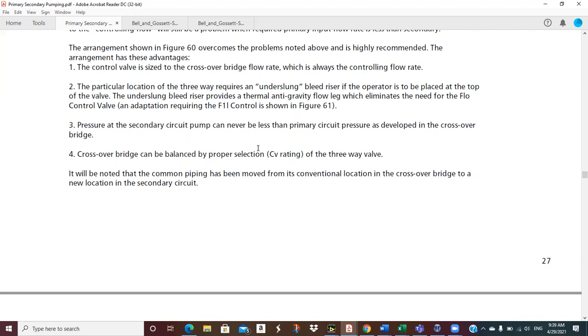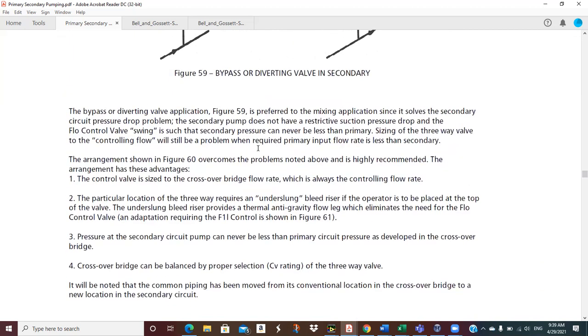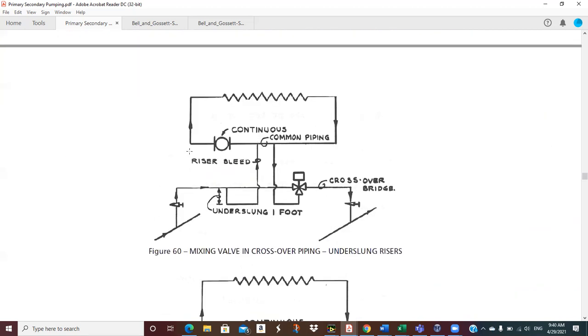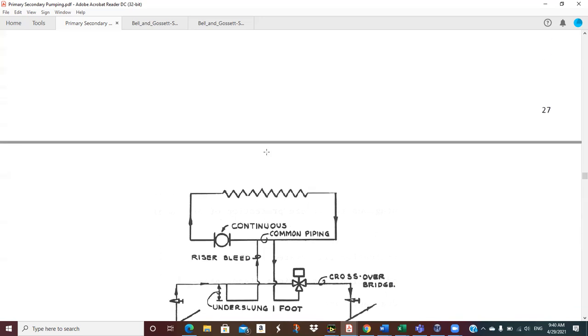Pressure at the secondary pump can never be less than primary circuit pressure as developed in the crossover bridge. And so remember, this is the point of no pressure change, the connection at the common pipes, I guess it's up here. And so when this pump operates, there'll be a slight pressure drop here, but then we get the increase in pressure all the way around here. So now that comment is not really true from this point to the pump, but you make that as small as possible. So in general, it is true.